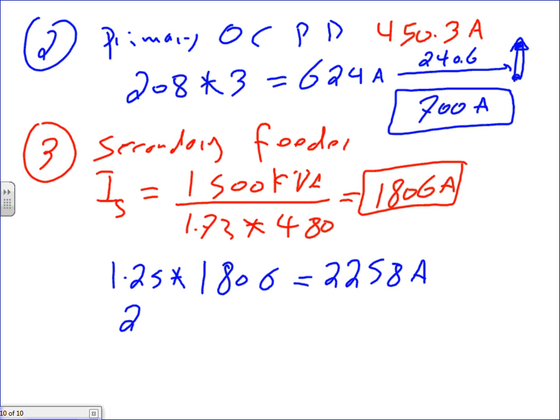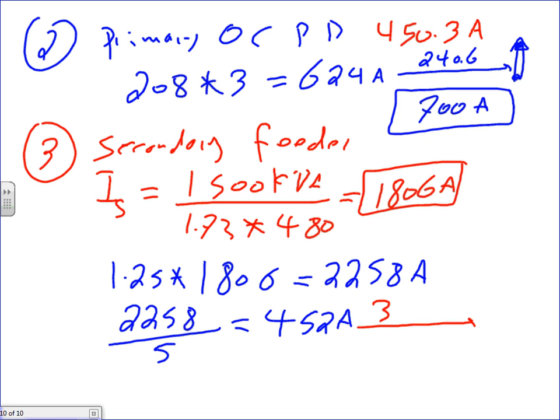So to cable it, I have 2258. I want to divide by 5, just because I'm the authority having jurisdiction. You can divide by any number. That will end up with 500 amps. Am I right here? No? How much? 452 amps. Okay? And then if you take this one to 310.16. Now, why 16? Because that's the low voltage side. What do you come up with? 700 kcmil.